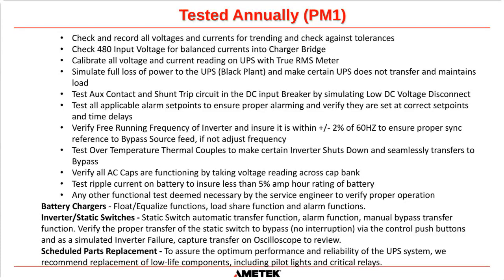For battery chargers, we'll check your float equalize function. And if you have chargers in parallel, we check the load share function. Now, depending on whether you have active or passive load sharing, in truth, if you've seen any of my previous presentations, you know that I don't particularly like forced load sharing. It can cause many issues to be perceived on the system when there's no issue there. What I mean by that is, it's very difficult to get two chargers to share the load, especially at low currents.